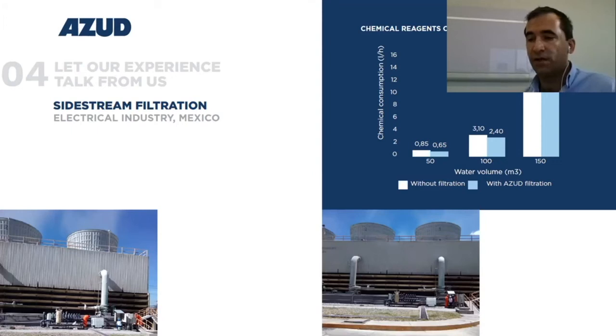After the AZUD disk filter installation, the company managed to reduce the chemical reagents and makeup water, improving the cooling system performance, with an average saving of 23% of chemical reagents in their 3 cooling towers, 50% reduction in their downtimes, and all this with payback in less than 2 years. In the end, AZUD filtration solution helped the company not only in terms of operational costs, but also allowed them to focus their efforts on their own production processes and not just the utility performance.